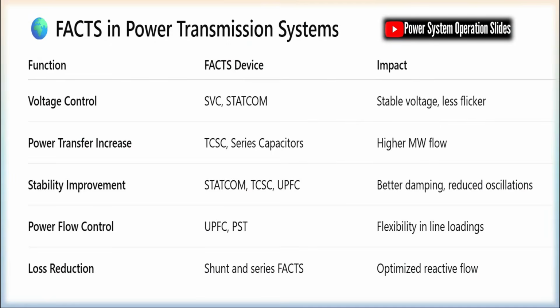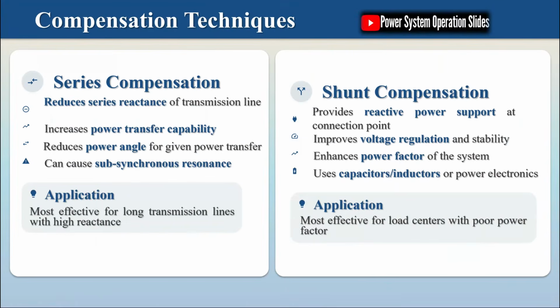One limitation of SVCs is that their reactive power output is dependent on the system voltage. The reactive power supplied by an SVC is proportional to the square of the system voltage. Q is proportional to V², which means that during low voltage conditions, when reactive power support is most needed, the SVC's capability is reduced. Additionally, SVCs typically require large inductors and capacitors, resulting in a significant physical footprint and relatively slow response time compared to more modern solutions.